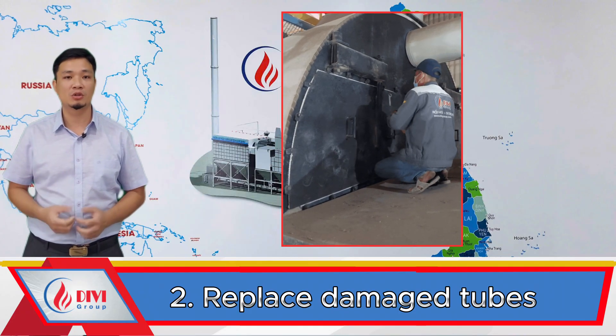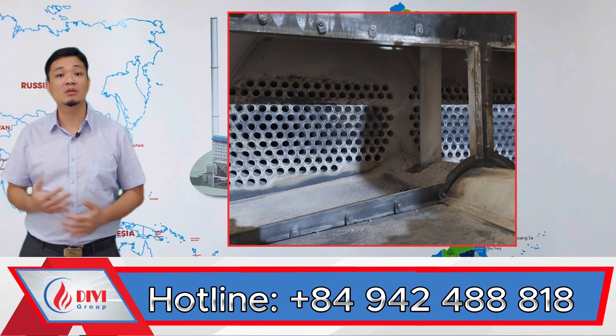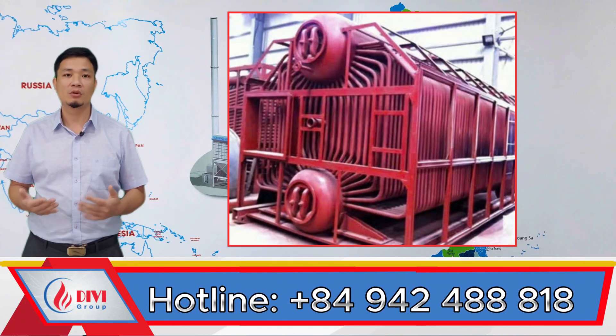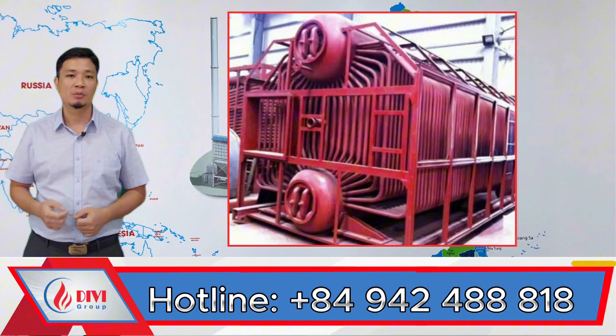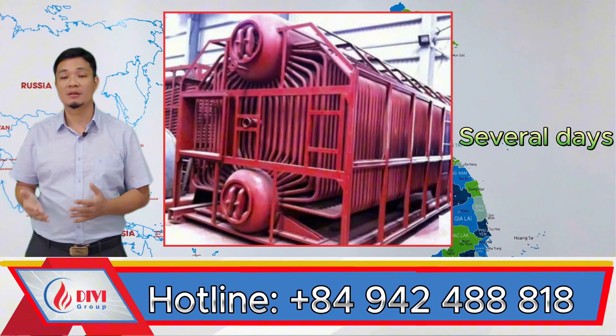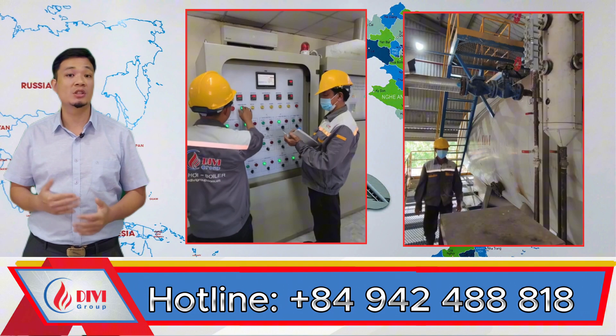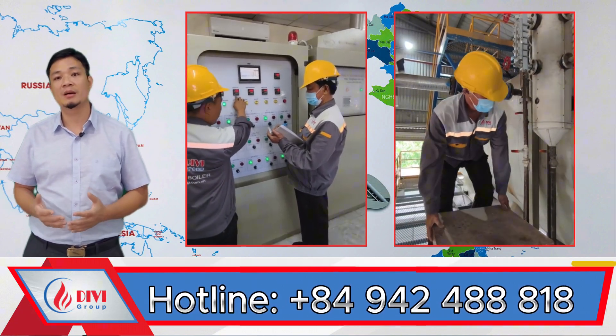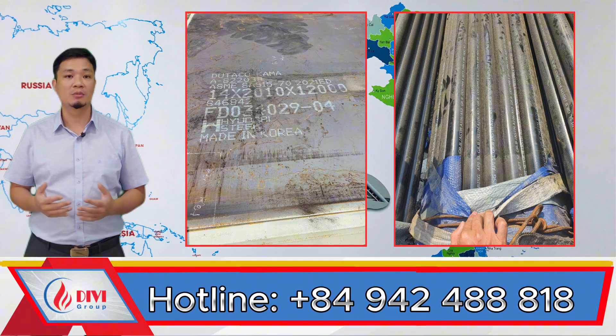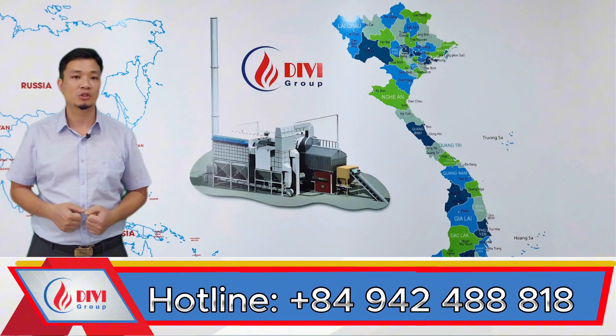Next is the tube replacement process in case of damage. With fire tubes, we simply open the smoke chamber door and, with a few basic mechanical steps — cutting and welding — we can replace an entire bundle of fire tubes very easily, or even replace just one or a few specific tubes if needed. In contrast, with the water tube design, it's very difficult, and in many cases impossible, to replace individual tubes in the convective section. If one tube fails, the entire bundle has to be replaced, and that process can take several days — making it one of the major drawbacks of the two-drum water tube boiler. That said, things have improved greatly today. Thanks to years of accumulated experience, structured training programs, and much better steel quality, these boilers can run for 15 to 20 years before needing a full tube bundle replacement.